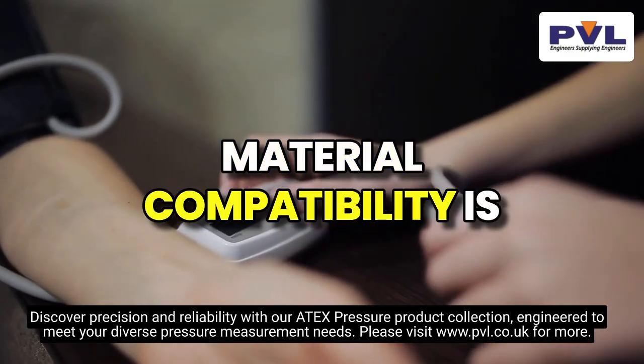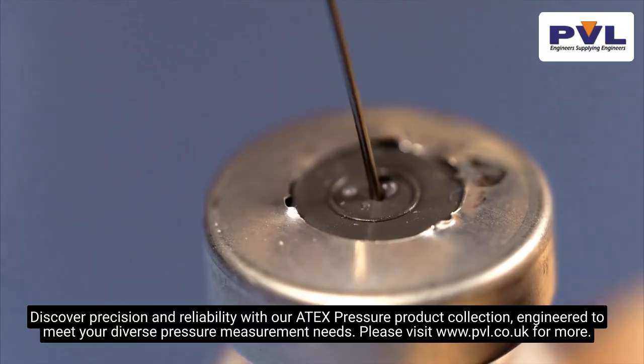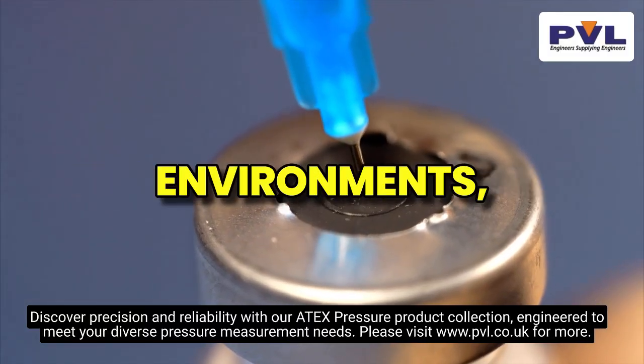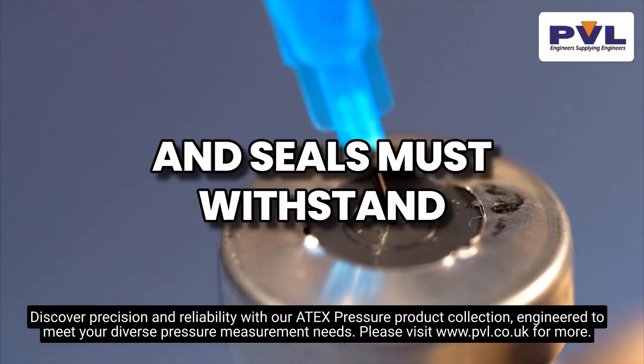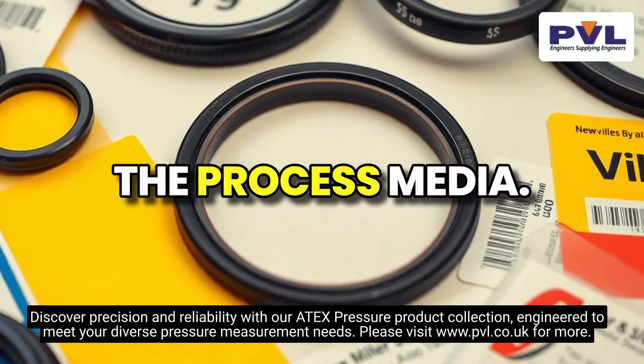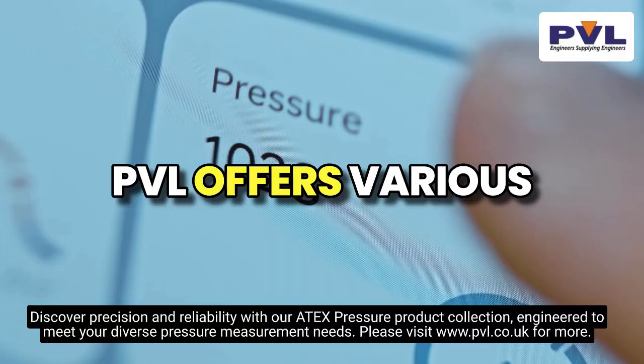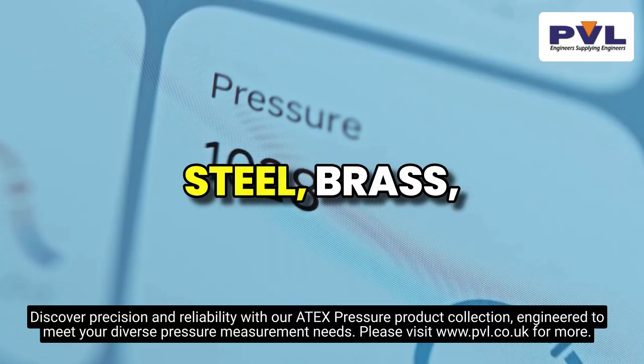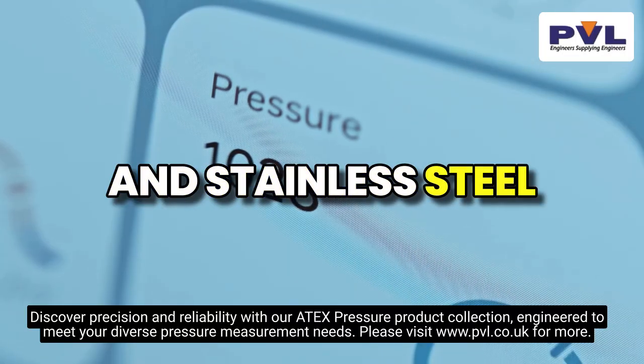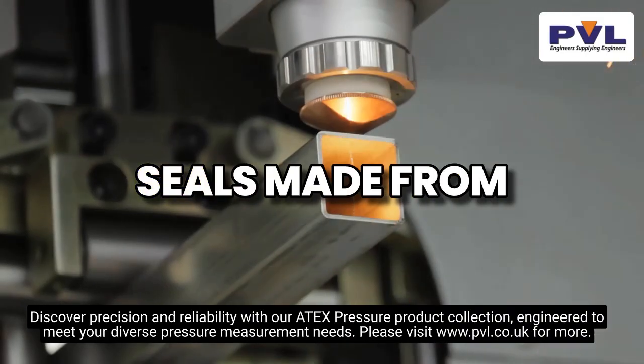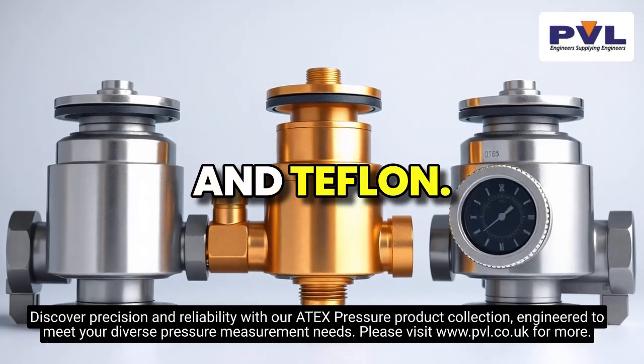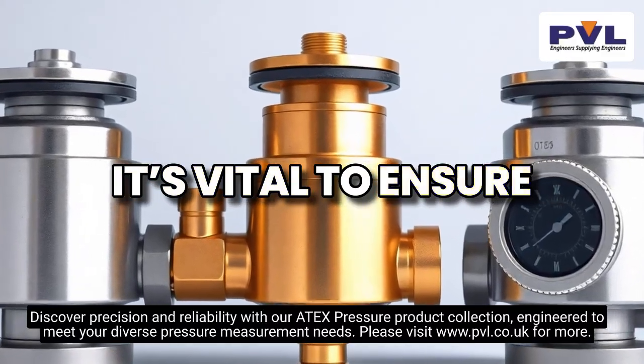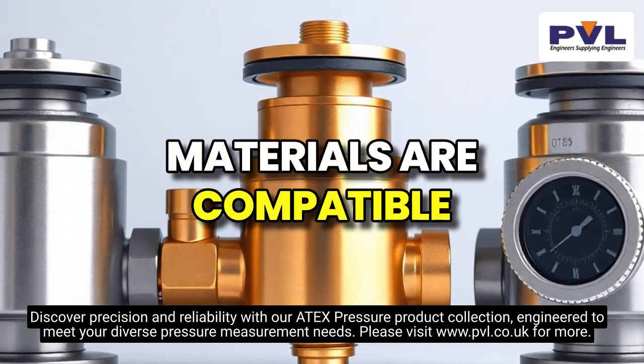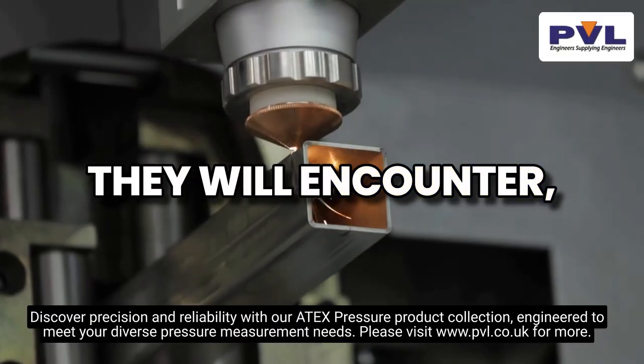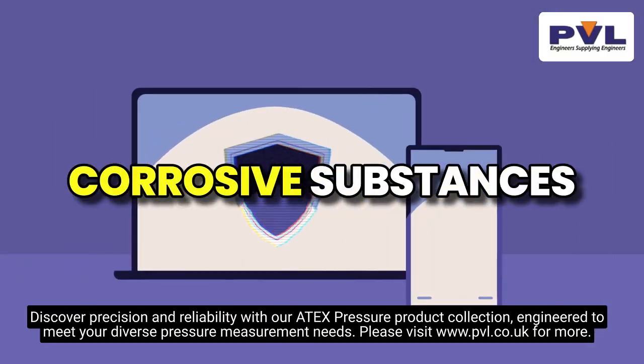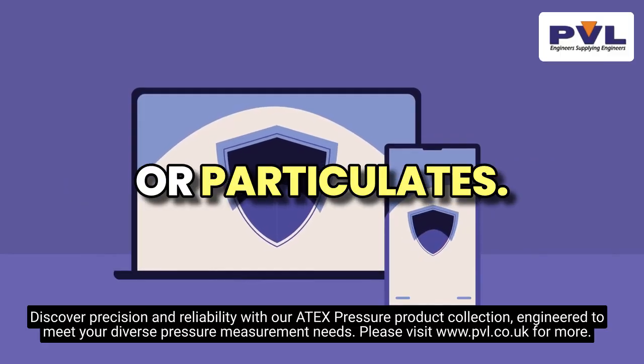Material compatibility is another critical factor. In harsh or corrosive environments, the wetted materials and seals must withstand the process media. PVL offers various options, including steel, brass, and stainless steel bodies, along with seals made from materials like Viton and Teflon. It's vital to ensure that the selected materials are compatible with the fluids they will encounter, especially in cases involving corrosive substances or particulates.